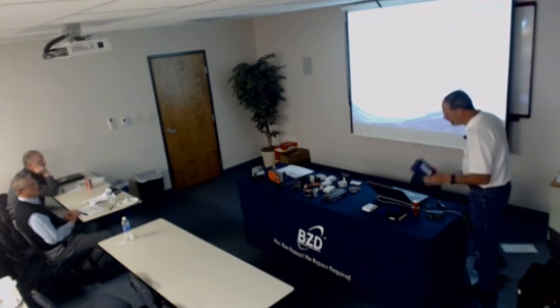Lon is a lot more friendly when it comes to what we call peer-to-peer, meaning if I have 2 of these controllers and I want them to share data, Lon just does that naturally. It's just what it does. You can do it with BACnet if you fight it hard enough. If there's a front-end PC, if there's a Tridium panel front-end, then it becomes real easy. But if you're just having 2 pieces of equipment, you want them to share data, Lon does it much cleaner, much faster. It just does a better job.